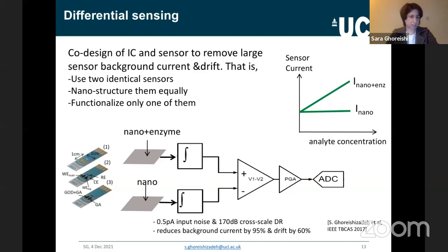We actually implemented this, and I went all the way to prove this idea. We managed to show that with this differential sensing technique, we can reduce the background current by up to 95%. Not only that, we can also address the drift of the sensor and compensate for it by up to 60%. Additionally, this instrumentation circuit had one of the highest dynamic ranges among such circuits - when we published this, it was 170 dB, covering a scale from the picoampere range all the way to tens of microamperes.